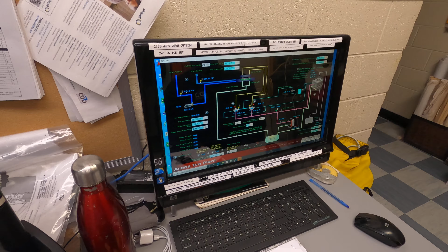And you know, when talking to the operators, if those two numbers are quite a bit out from each other, or too close or too far away, that's just telling me, do I have a problem with my chiller because I'm not getting enough heat out of it? Am I running the brine too fast? So I'm either not picking up heat out there, or it's going so fast through the chiller that it's not giving it up quick enough. So the average rule of thumb is about a 3 degree Fahrenheit differential between your supplies and returns if you're doing a good job at heat recovery.